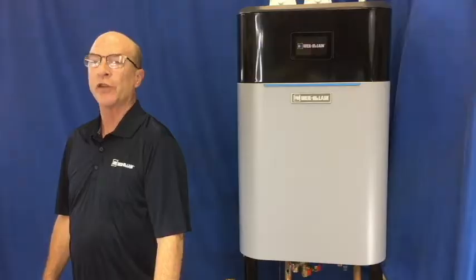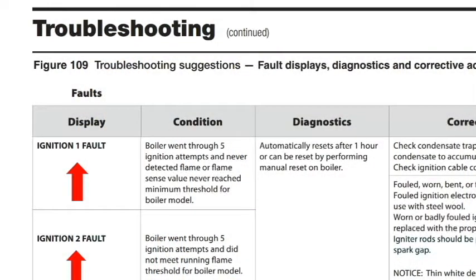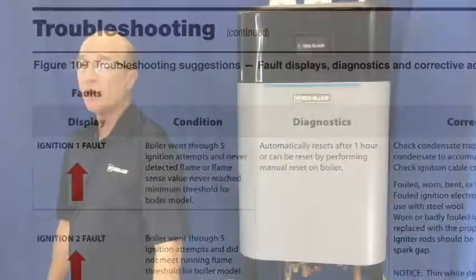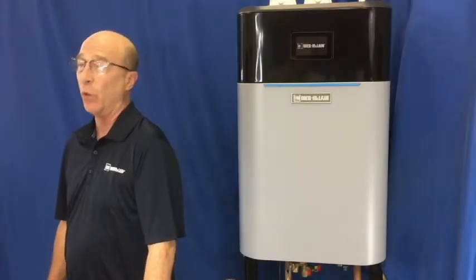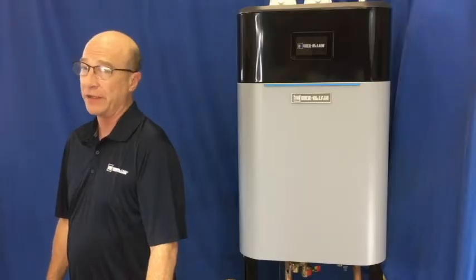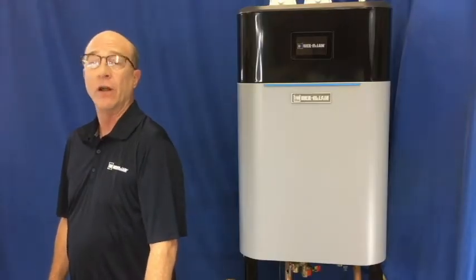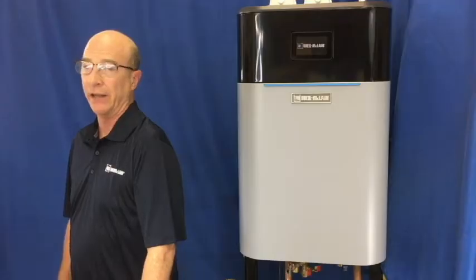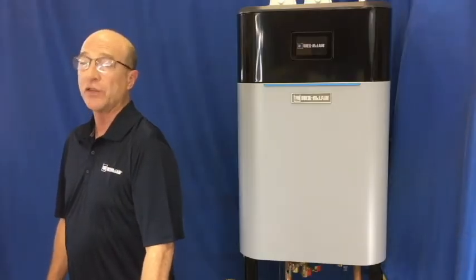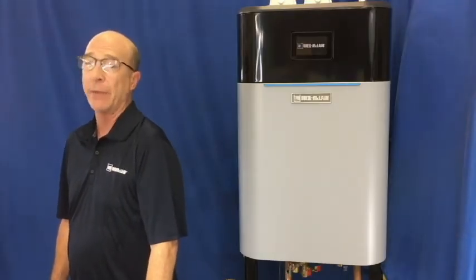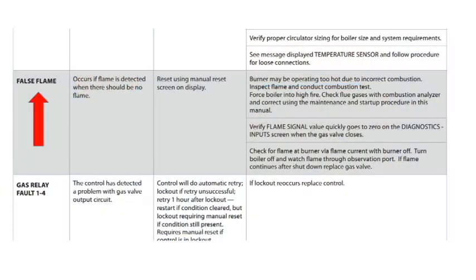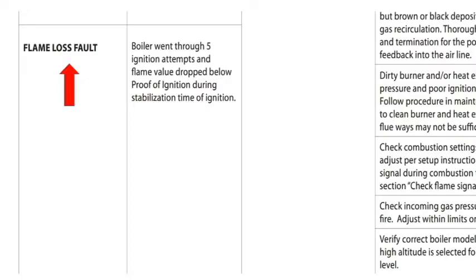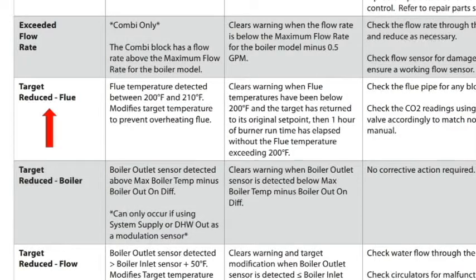The most common fault you could see would be an ignition fault. If the air-fuel mixture is well out of range, the boiler most likely will not fire. Or if it does, the flame signal may be so low the boiler will not stay lit. Other faults that may be caused by improper air-fuel mixture are false flame, flame loss fault, and target reduced flue temperature.